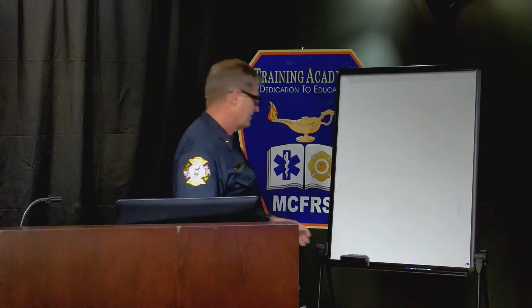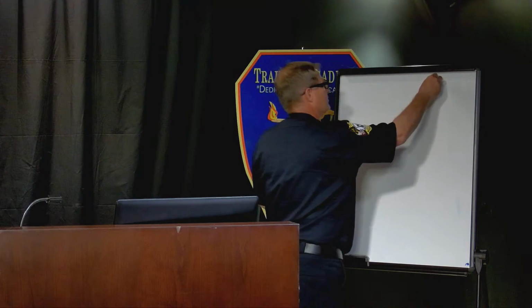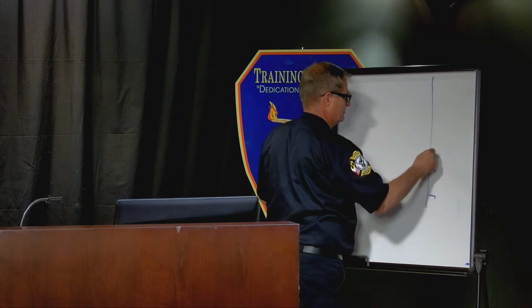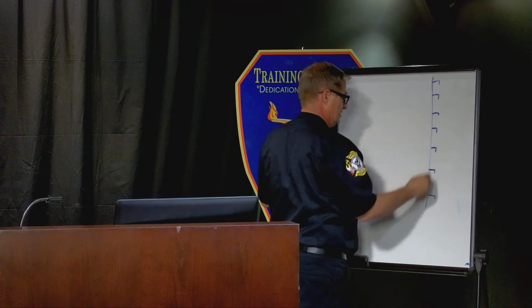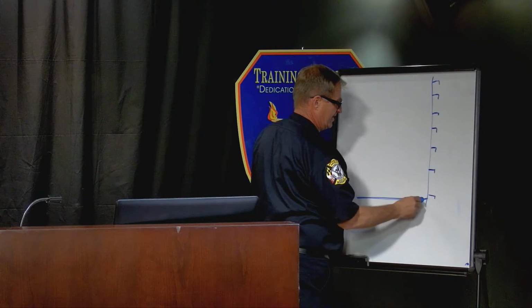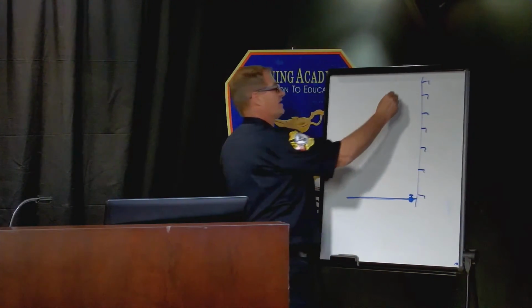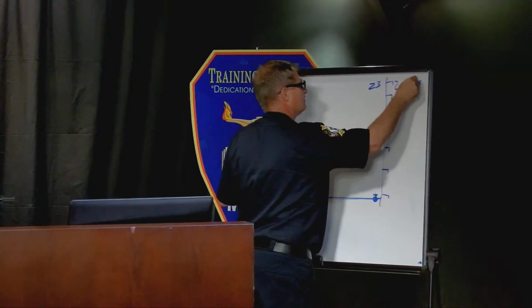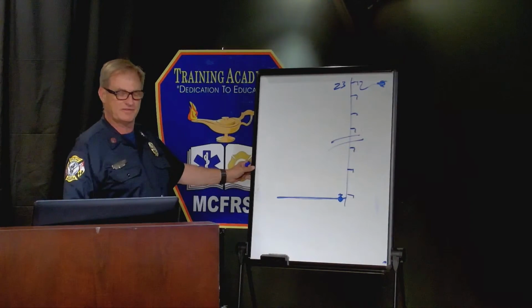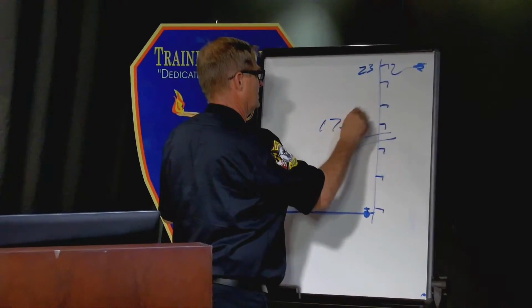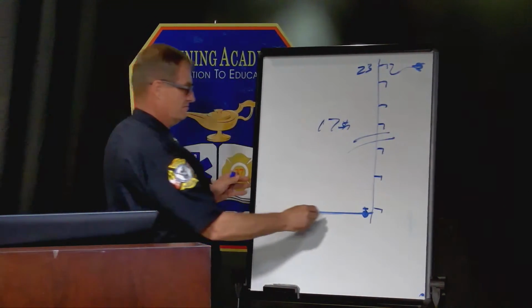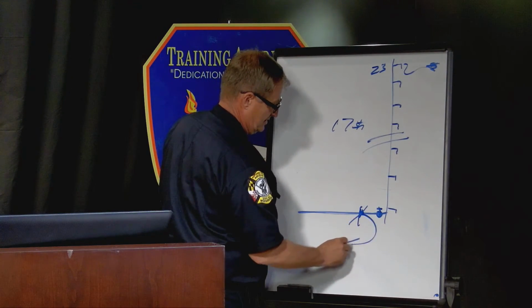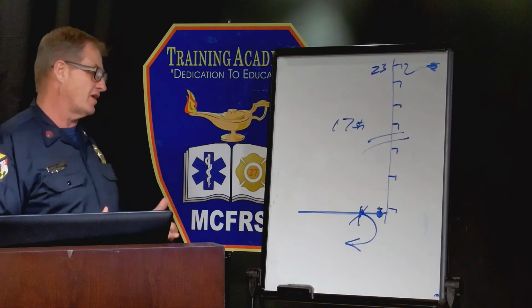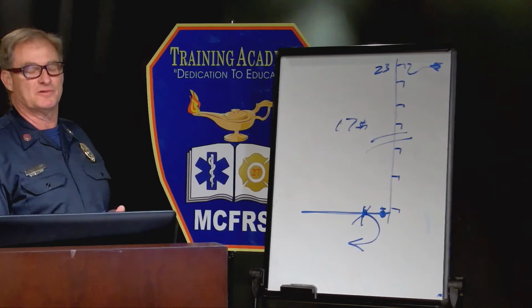It just might not. So I'm gonna draw on the board, and I'm gonna diagram this on the board as to what our first workaround really could have been. So we've got our riser here, and our fire hose valves, and we know our bulk feed main comes here, and we know we have a valve right here. Okay, and we knew that 23's crew were doing their thing and flowing water up here, and I think we're 17 stories if I remember correctly. They're doing their thing, and everything's just fine. And all of a sudden, our double elbow here goes, and this is an open 6-inch line, probably flowing, I bet, 1,200, 1,300 gallons of water a minute.